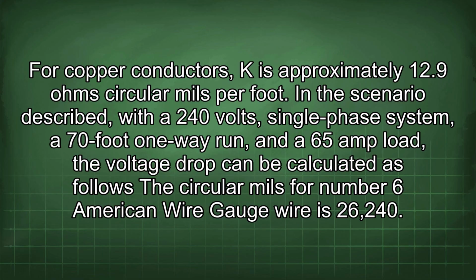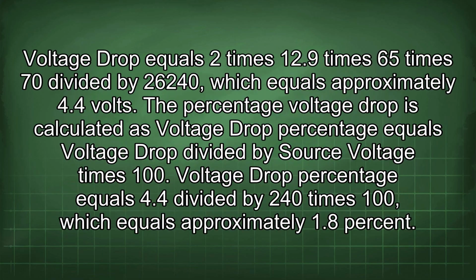In the scenario described, with a 240 volts single-phase system, a 70-foot one-way run, and a 65 amp load, the voltage drop can be calculated as follows. The circular mils for number 6 American wire gauge wire is 26,240. Voltage drop equals 2 times 12.9 times 65 times 70 divided by 26,240, which equals approximately 4.4 volts.